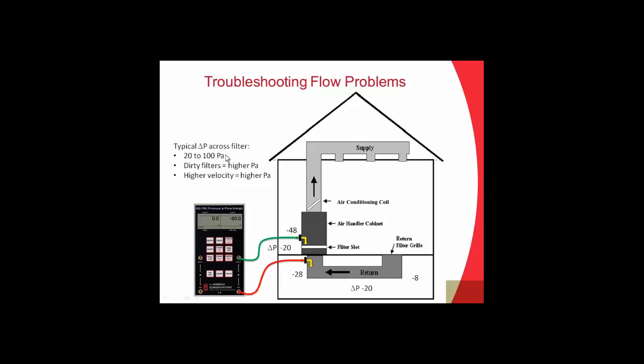So typical pressures across filters that you'll see are anywhere from 20 to 100 pascals, depending on if it's a thin pleated filter or maybe it's a 3-inch wide or a 4-inch wide filter. Pleating is going to have less of a pressure drop. Dirty filters are going to cause higher pressures. Higher velocities are going to cause higher pressures. And a lot of times, when you buy filters, it'll show what the pressure drop is for a certain CFM. But if you have higher velocities, you're going to have higher pressures than what it's stating there. So you kind of need to know what your airflow is in order to know how much of a pressure drop that furnace filter is going to cause. So we've got the pressure across the filter is negative 20.